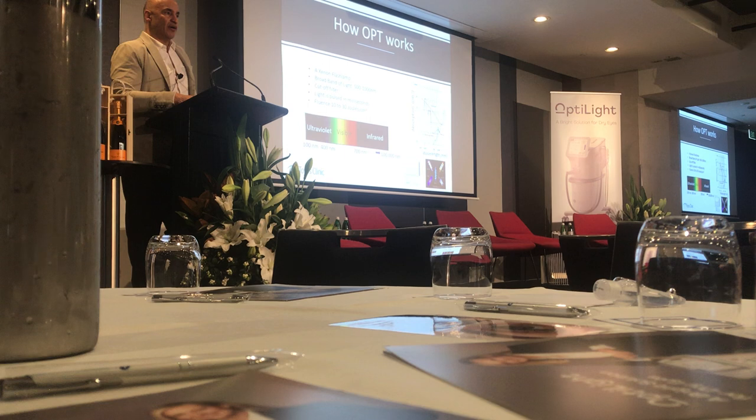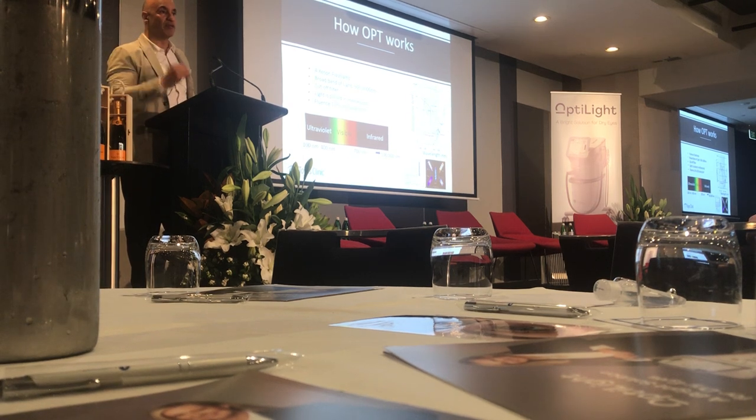You can adjust the joules from 10 to 16 to get the same effects. Once you start getting above 16 joules, you start to do some damage to the meibomian gland. That is your cutoff when talking about energy levels at the lid margin.